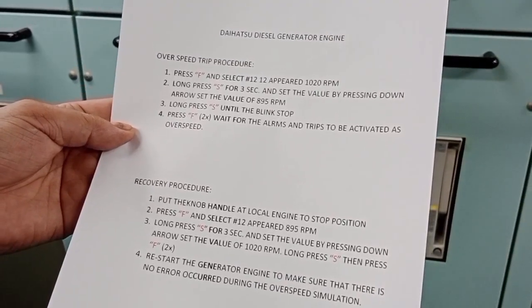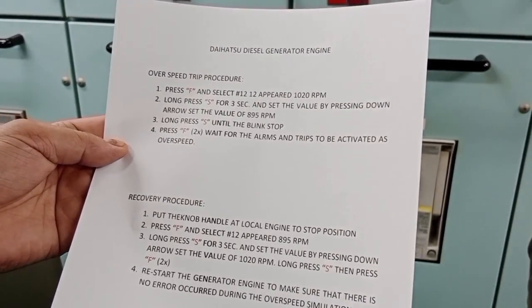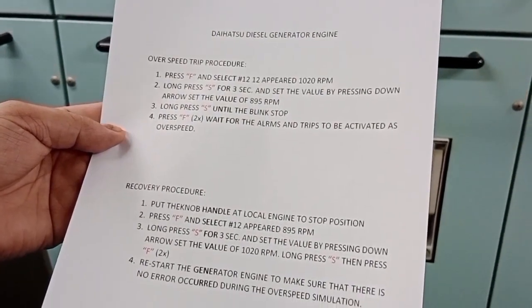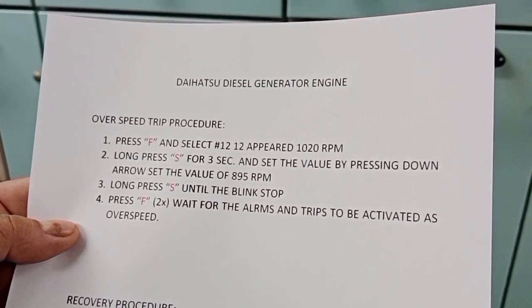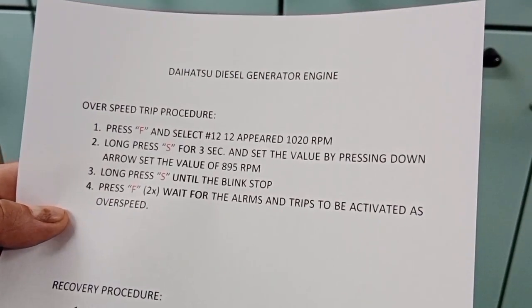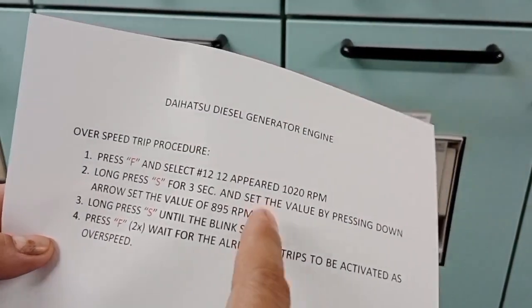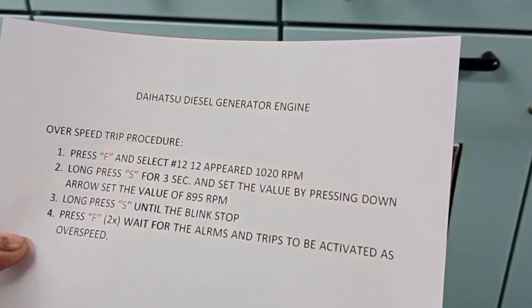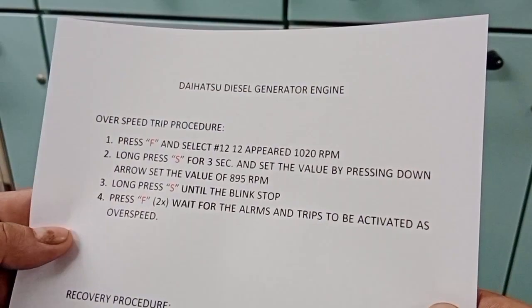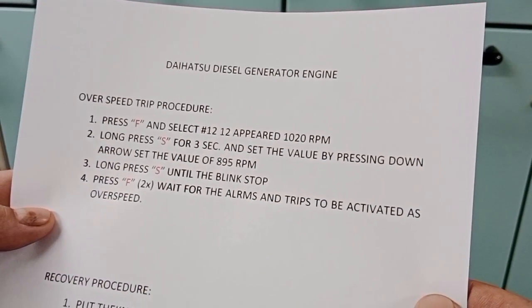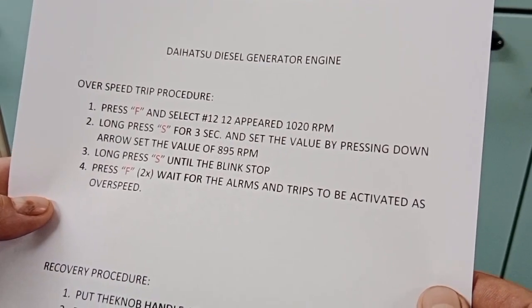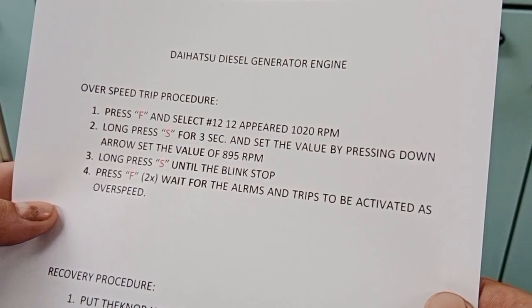Next, we are conducting the overspeed test of the generator engine. This is the procedure: number one, press F, select number 12, set to 1020 RPM. Number two, long press S for 3 seconds, set the value by pressing down arrows to set the value of 895 RPM. Number three, long press S until the blinking stops. Number four, press F two times and wait for the alarms and trip to activate as overspeed.